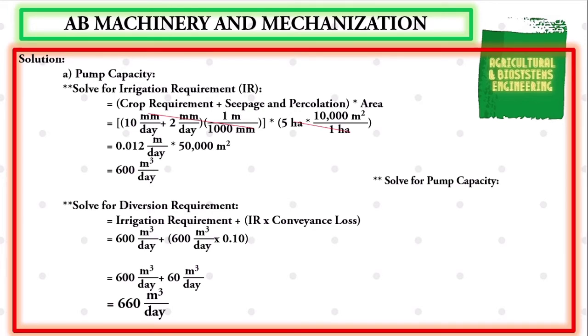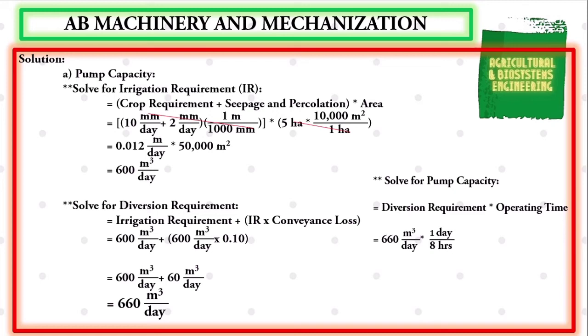We can now solve for the pump capacity. The formula is: pump capacity = diversion requirement ÷ operating time. Substituting: 660 m³/day ÷ 8 hours/day, giving us a final value for pump capacity of 82.5 cubic meters per hour.